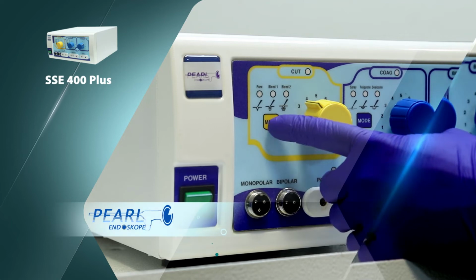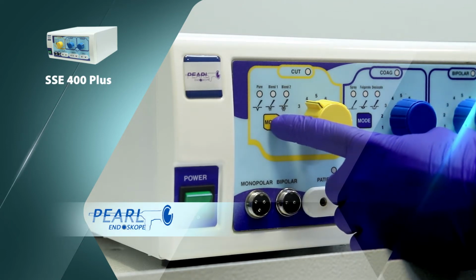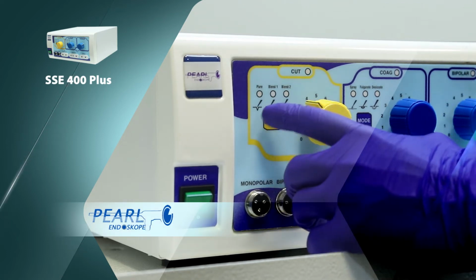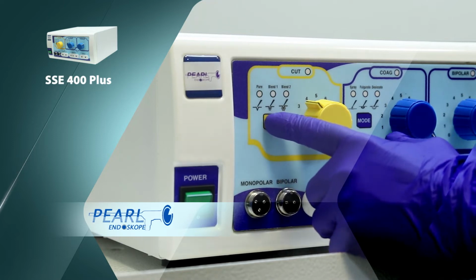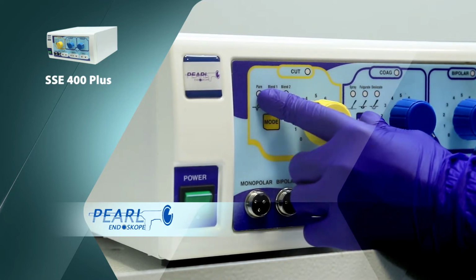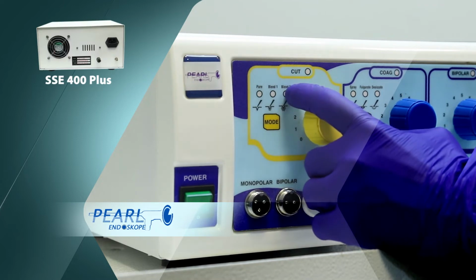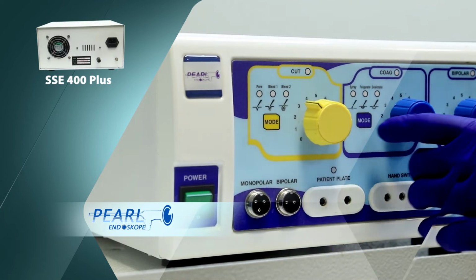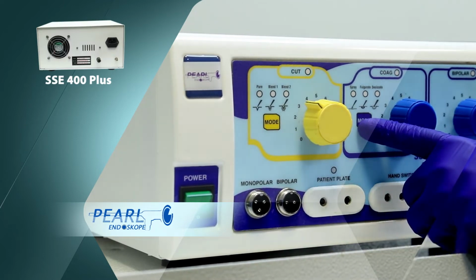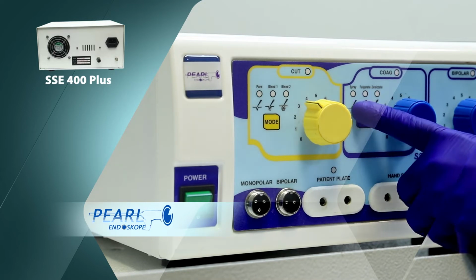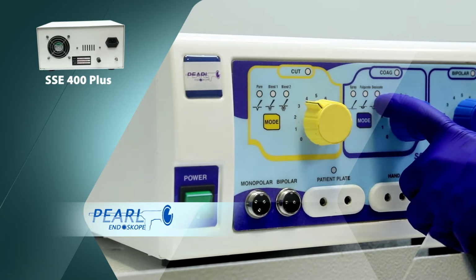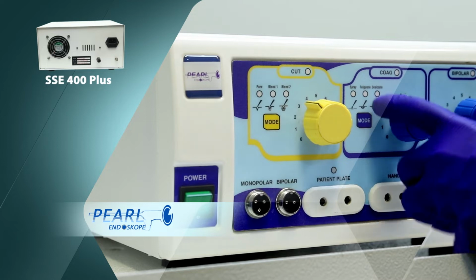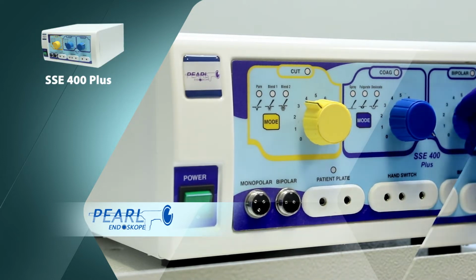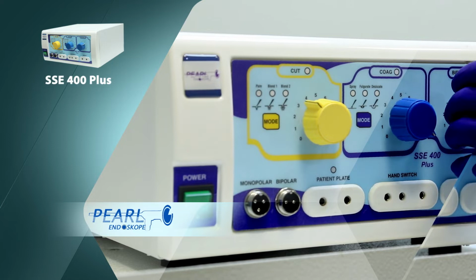This is the mode button under the cut calibration, which can be set to pure, blend 1 or blend 2. The mode button in the coagulation calibration can be set to spray, fulgurate or desiccate. The bipolar has no mode button.